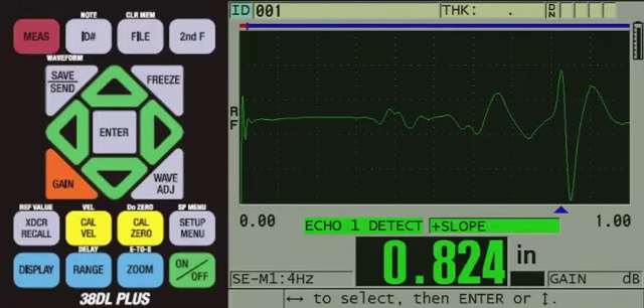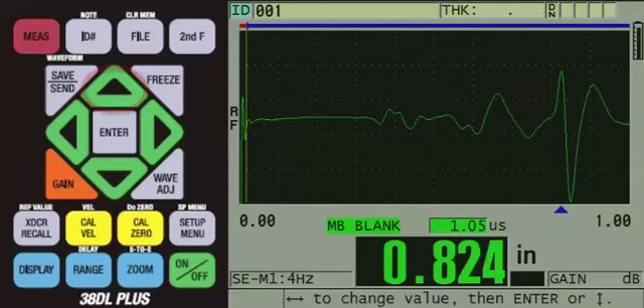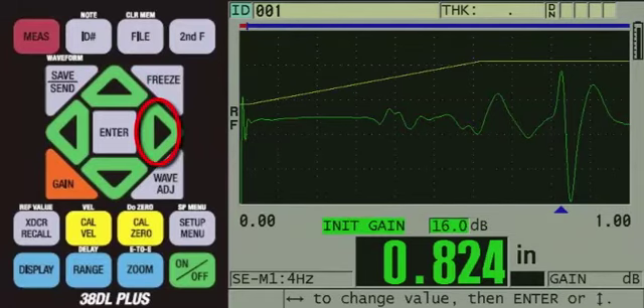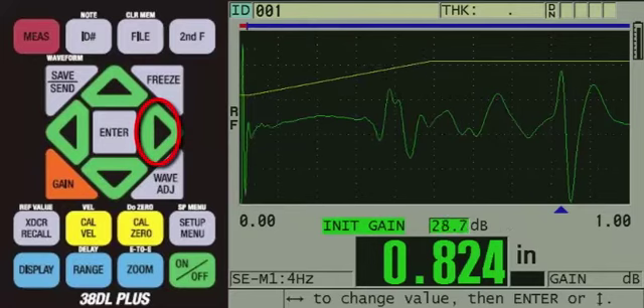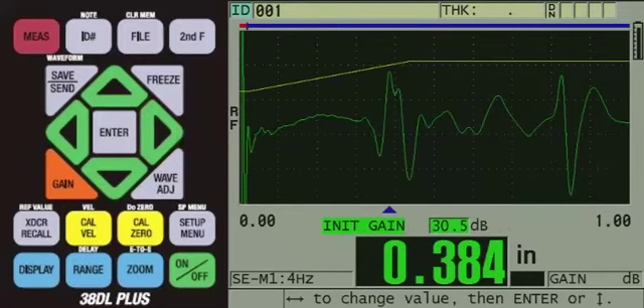The instrument is still measuring total thickness. This is due to the diameter of the transducer being larger than the diameter of the steel cords. Since the signal from the steel cord appears sooner in time, we need to increase the initial gain. To do this, press the up arrow to INIT gain, then press the right arrow to increase the initial gain. Keep pressing the right arrow until the signal from the steel cord is being detected. We are now making detection of what appears to be the correct signal.